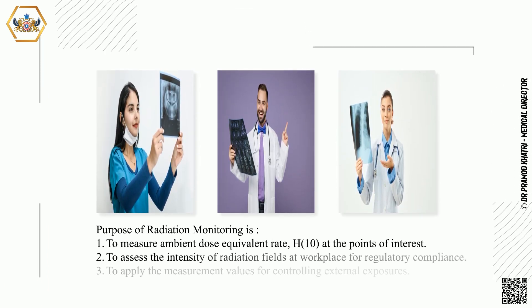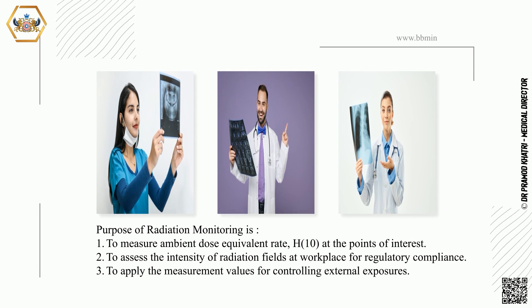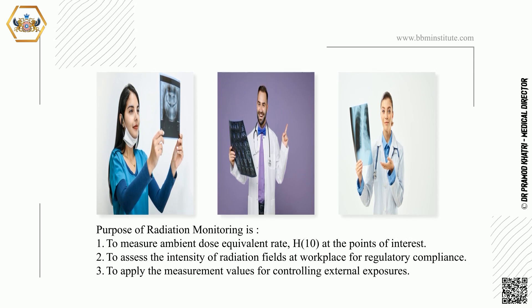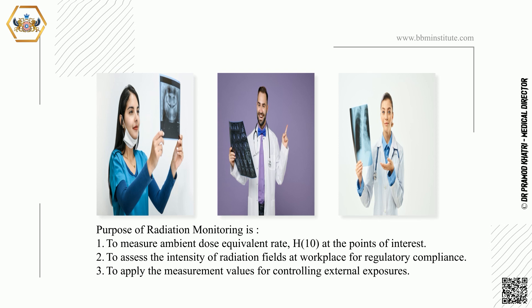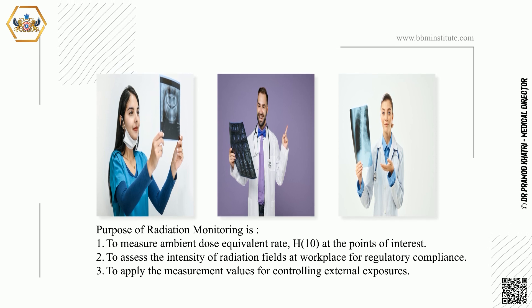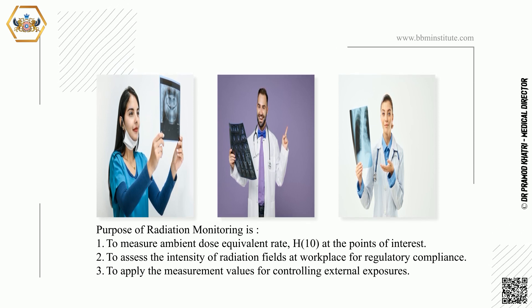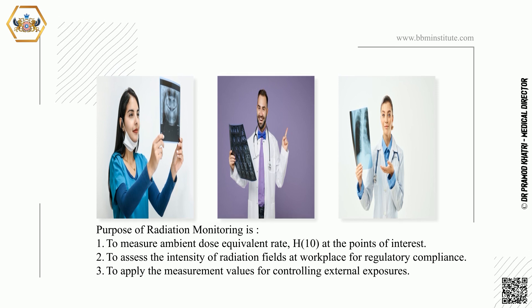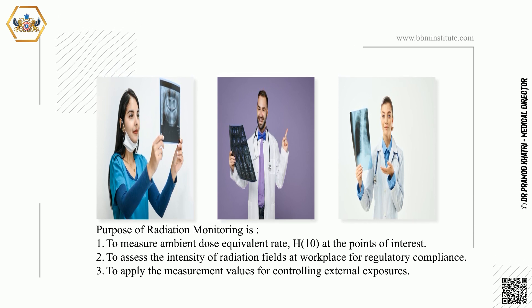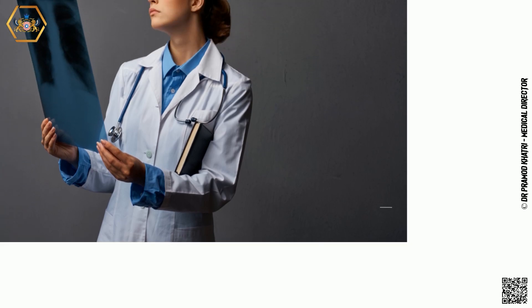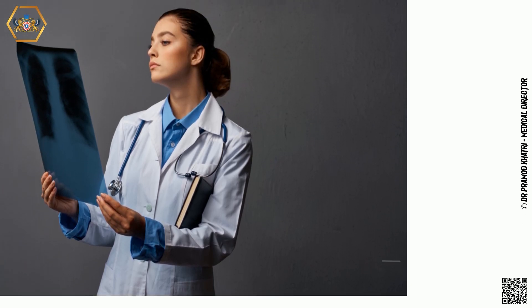The purpose of radiation monitoring is: first, to measure ambient dose equivalent rate at the points of interest; second, to assess the intensity of radiation fields at workplace for regulatory compliance; third, to apply the measurement values for controlling external exposures.